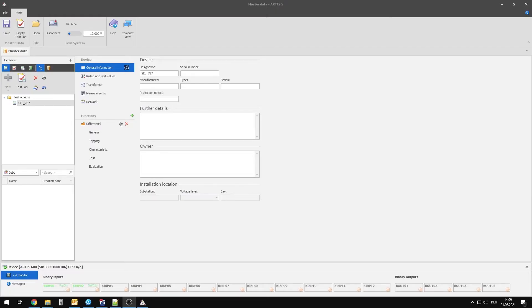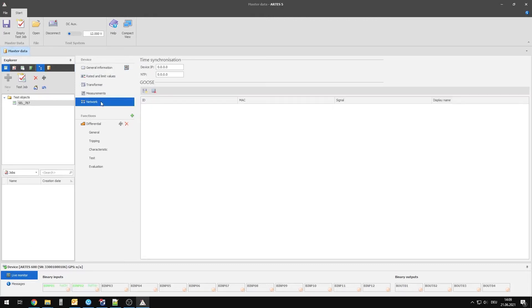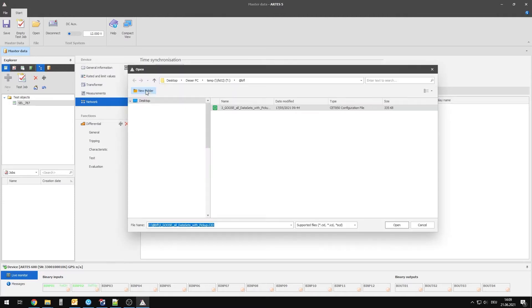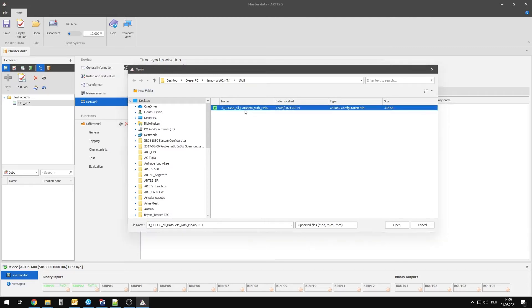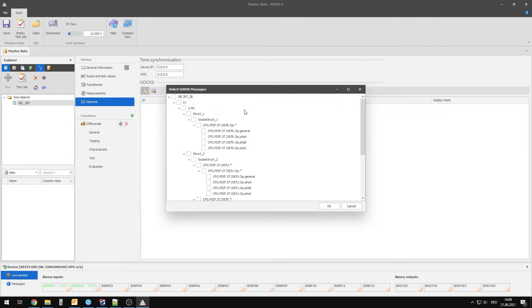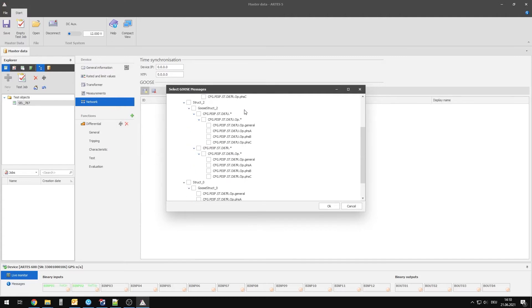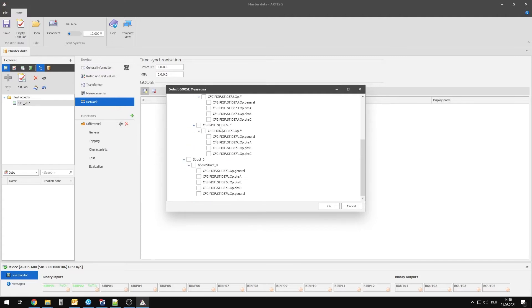To perform the test, the ARTES 5 software is started and the communication with the test system is established. Since countless goose messages can be distributed via the process bus, it is necessary to specify which messages or signals have to be recorded and evaluated before the test is started. For this purpose, the configuration file unique for each test object is loaded and the required signals are adopted into the software.